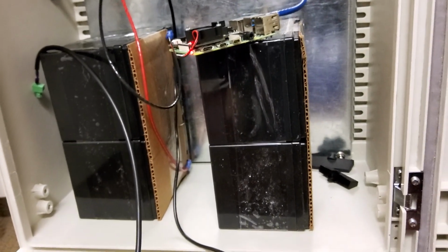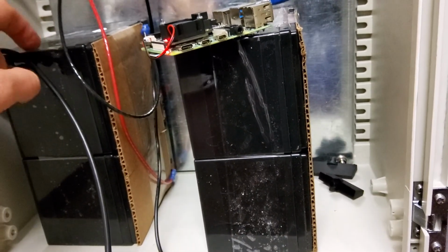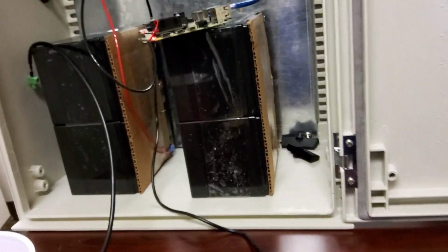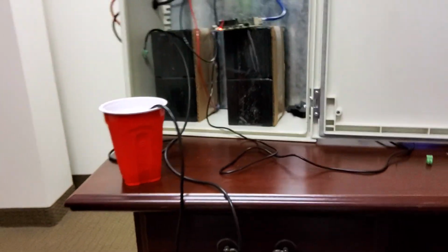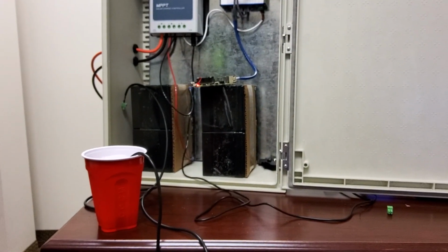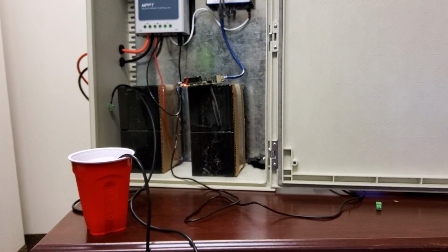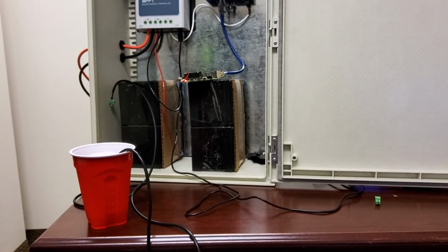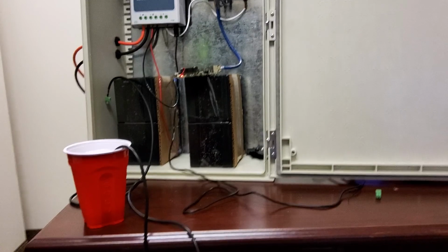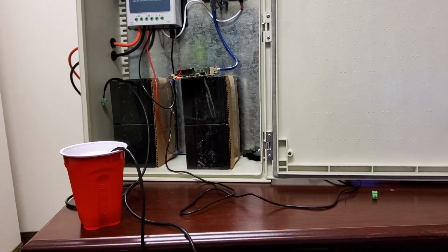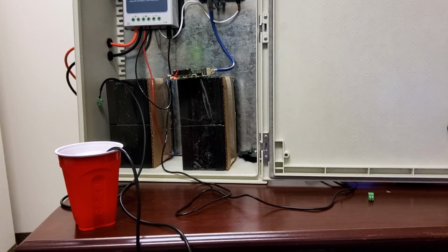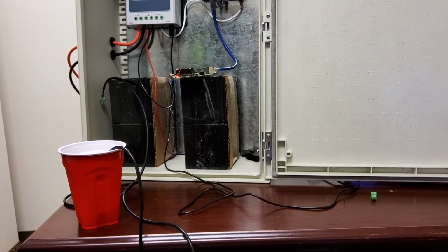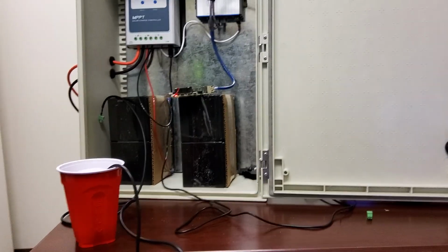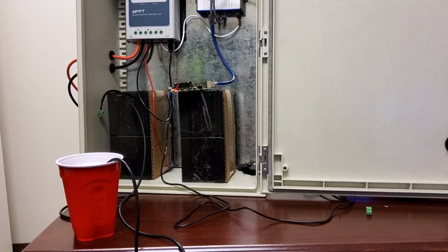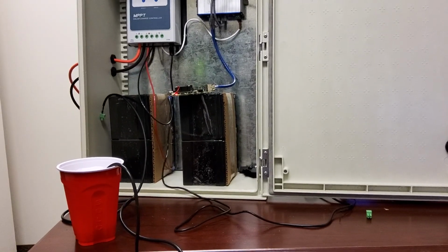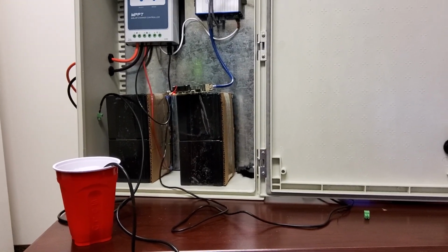The other thing I wanted to mention is before we were using lithium iron phosphate batteries, we were using AGM batteries, and they were not cheap. They were from a well-known manufacturer, and I'm not going to name any names, but they cost us more for those batteries than it did for these batteries. And we had a pretty high failure rate, and mostly because we would install these units in the field, and then the service contract would be up, and then we would remove them out of service and then store them.